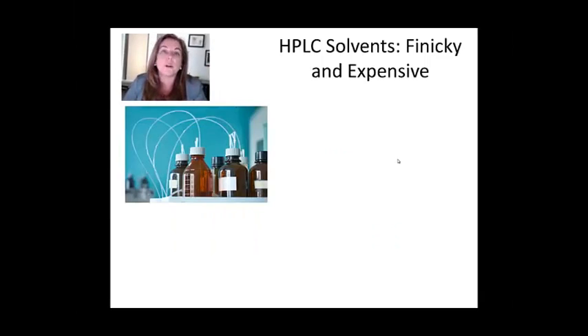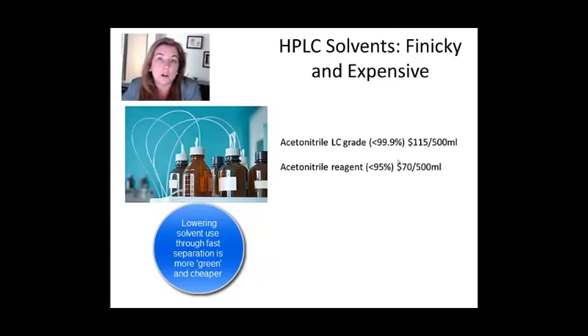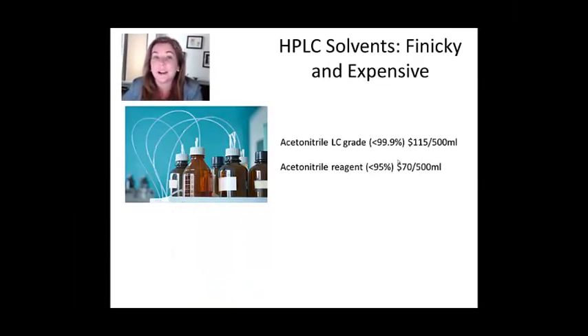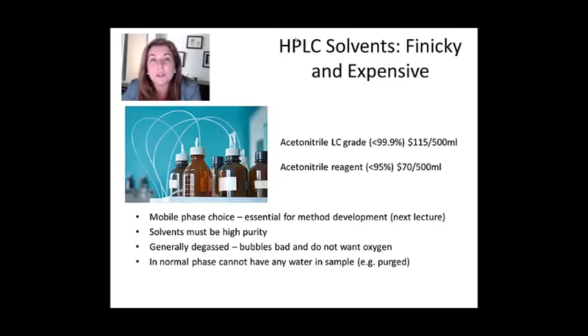Now, HPLC solvents are another really important component of the instrument, and they're very finicky and extremely expensive. So one of the reasons you like to do short chromatography experiments that don't last an hour is because it costs you a lot less in waste solvent. So you'll notice that these solvents need to be highly pure, which of course contributes to their cost. And these are just two examples of acetonitrile, a kind of go-to HPLC solvent to really get HPLC grade. The other thing you'll notice about the boxes are the funny straws coming out of them and the fact that they have lids on them, and that's really because they need to be degassed. These solvents cannot have any bubbles because a bubble has a different compressibility than the rest of the liquid, and it can cause a change in pressure and it can also cause a weird signal out of the detector. So you really don't want any bubbles in your system, so you generally degas. The other thing you also don't want is any oxygen, and you don't want any water. So handling those solvents and changing them can be a bit of a hassle.